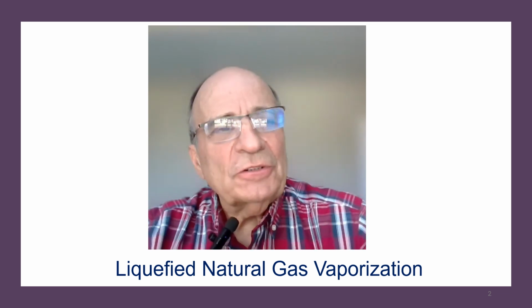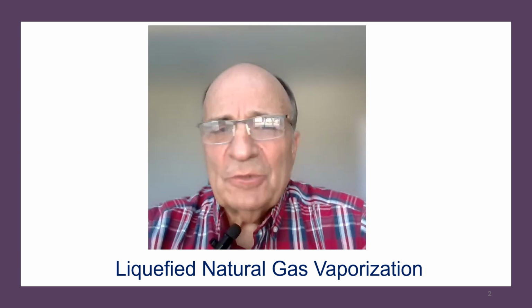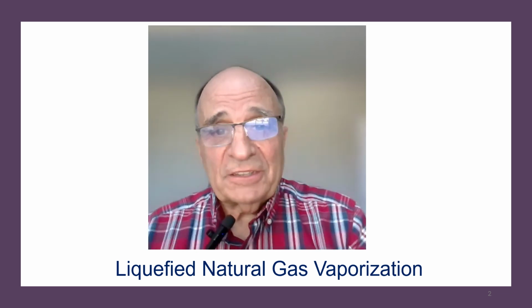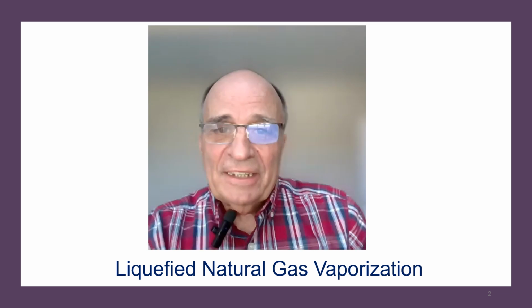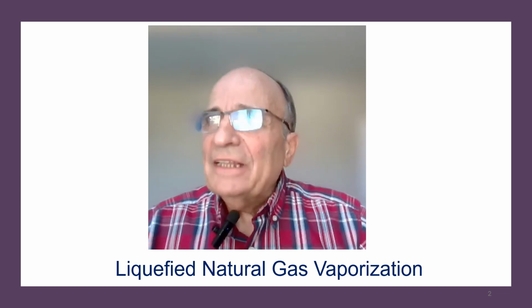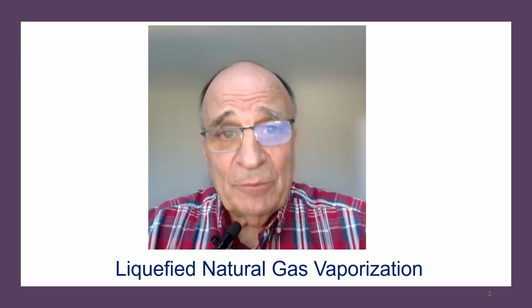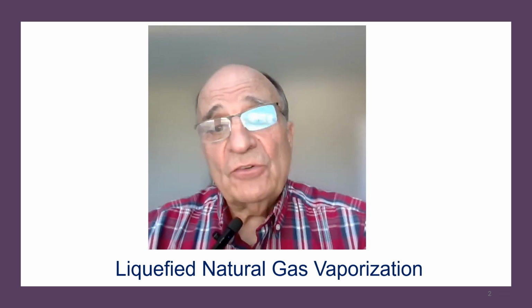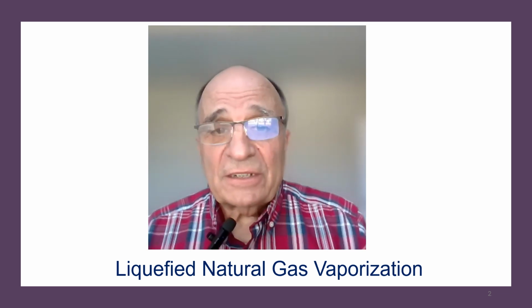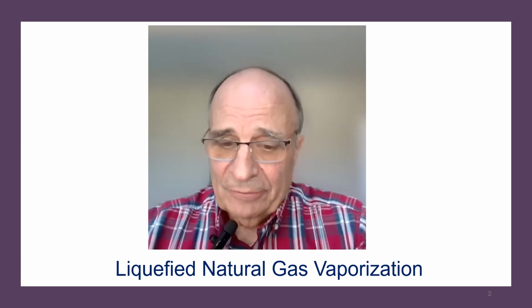When I first started this course, I thought, well, it's not too exciting, vaporization, but then I realized vaporization is the most critical function of an LNG facility other than an export terminal. Export terminals take LNG and put it onto ships and send it out. A few LNG facilities make LNG, store it, and put it into trucks and ship it out. But almost every other LNG facility, be it an import terminal or a peak shaver or a satellite facility, takes LNG, stores it, and then when it's needed, they vaporize it. And it's extremely important for that vaporization system to be ready to operate when needed.